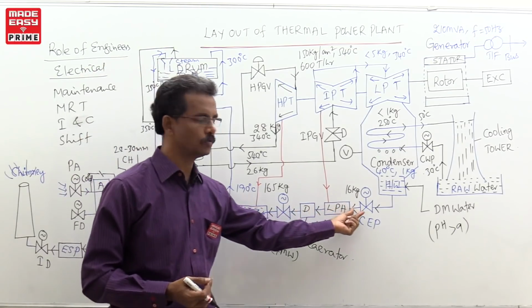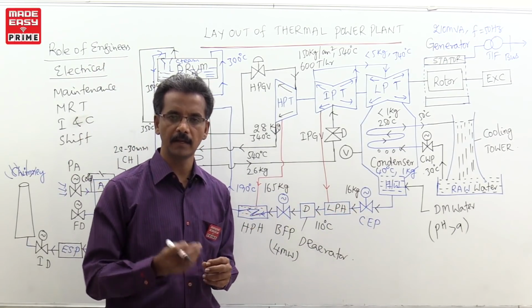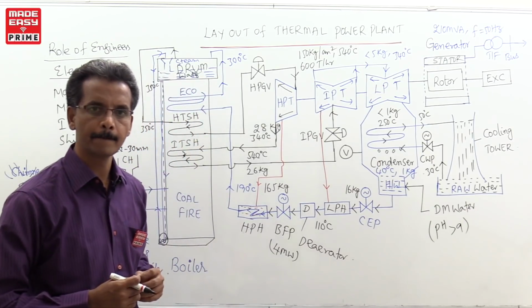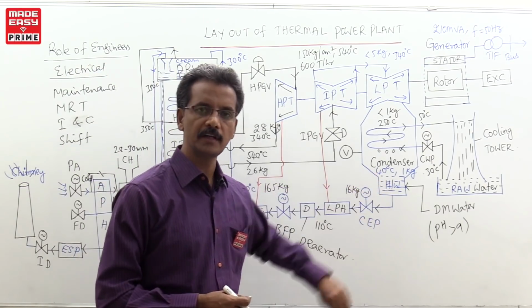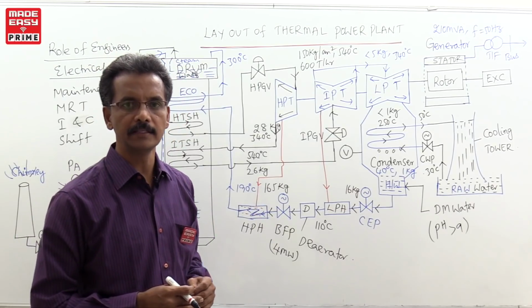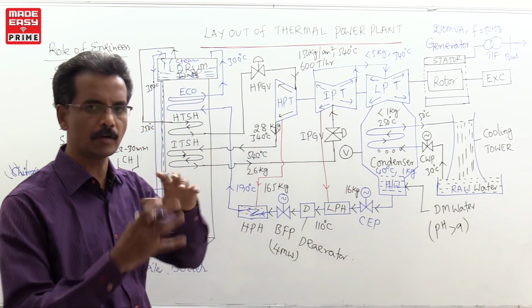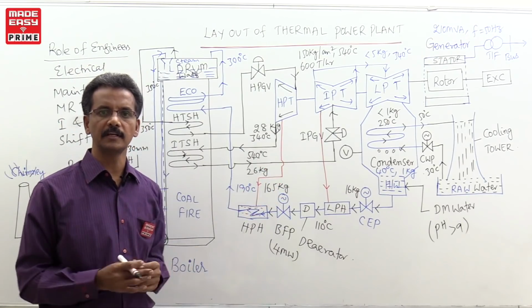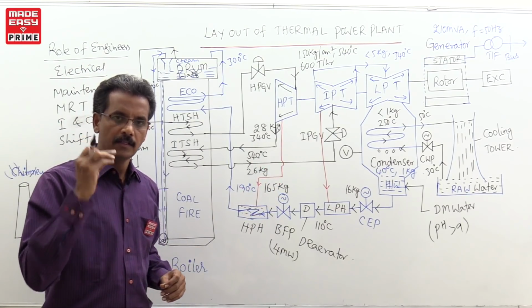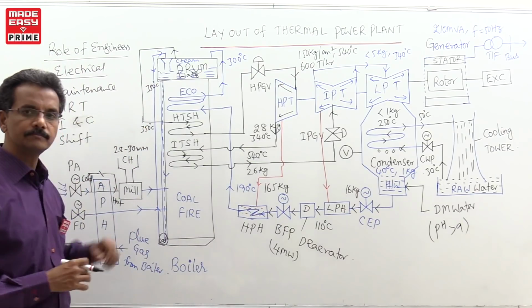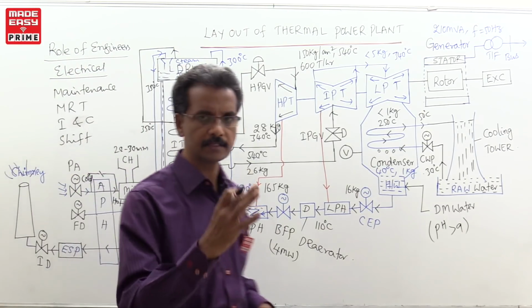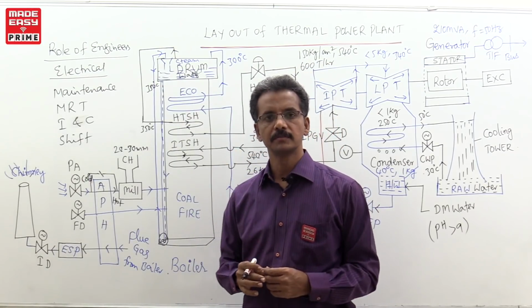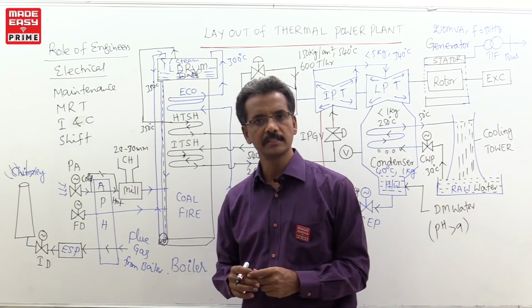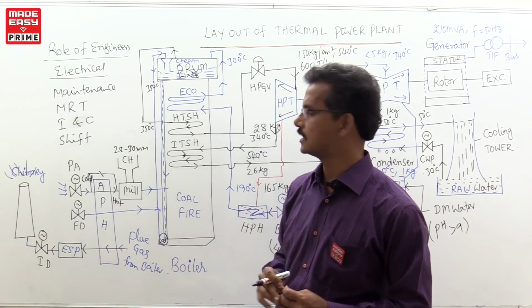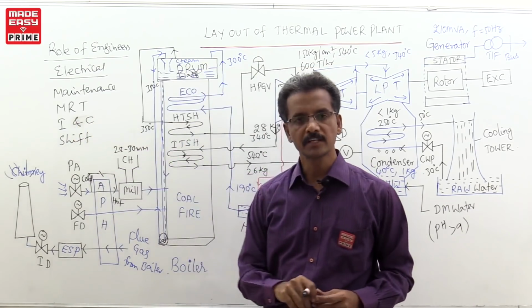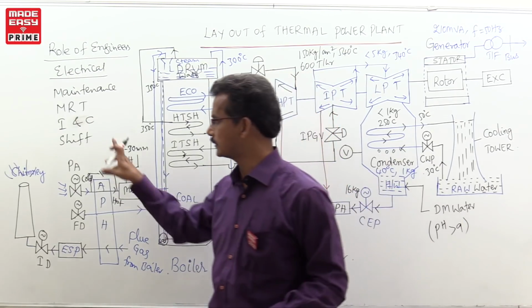And from the motor point of view, temperature based relays, thermal relays, are used, and other protection relays like overcurrent and earth fault relays. In the case of a transformer, the Buchholz relay. All the protection you have studied in regular class, they will look after, the MRT people. Not only relays, but circuit breakers and meters, ammeter, voltmeter, they will look after the healthiness of this equipment. Next one, instrumentation and controls. See, one of the interesting things.